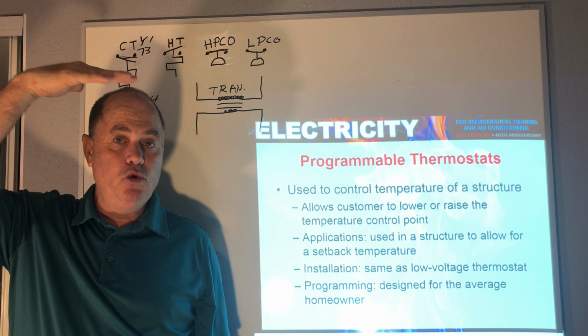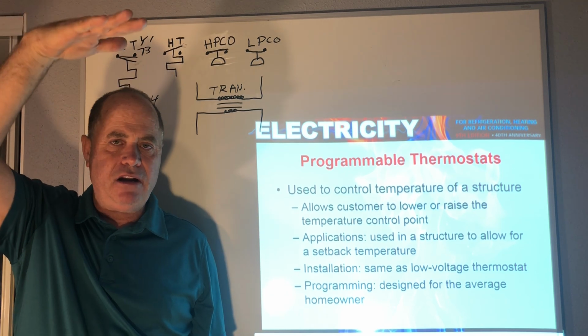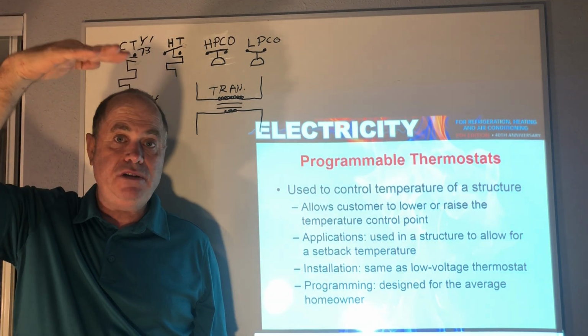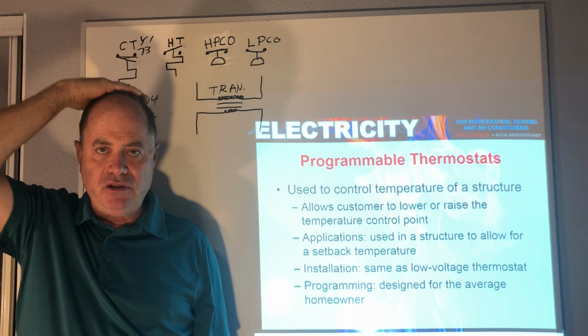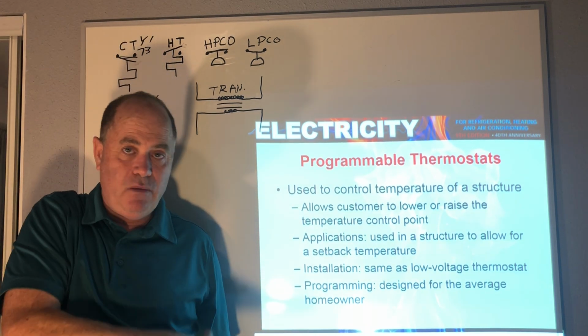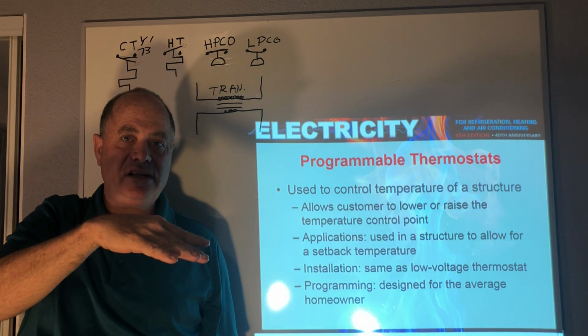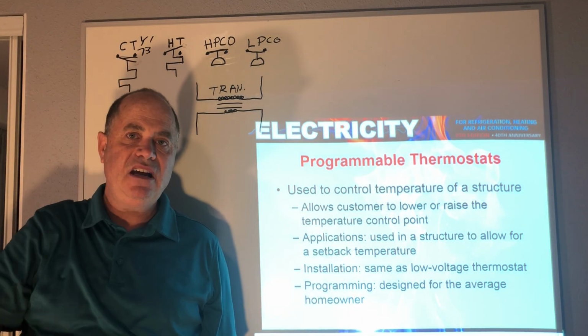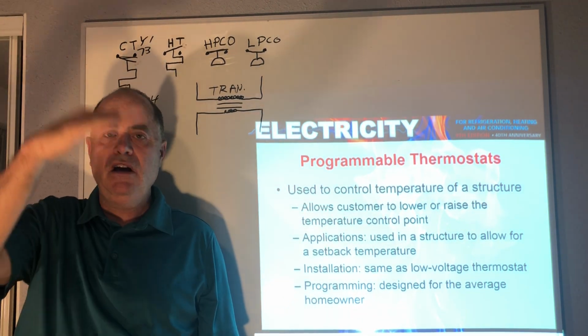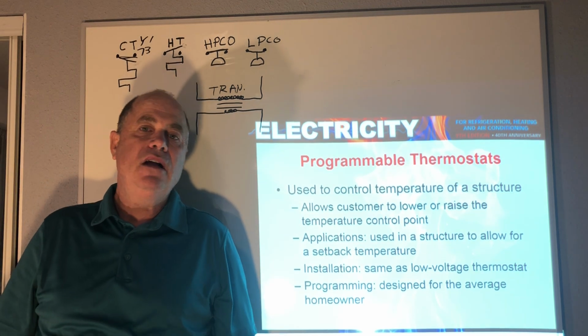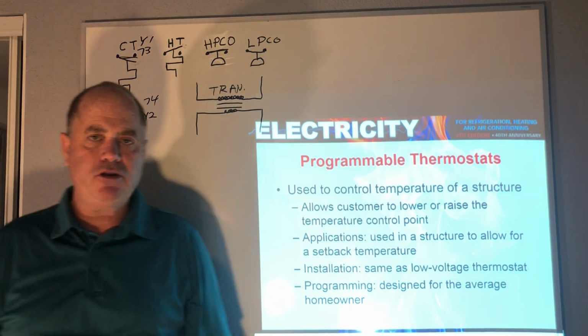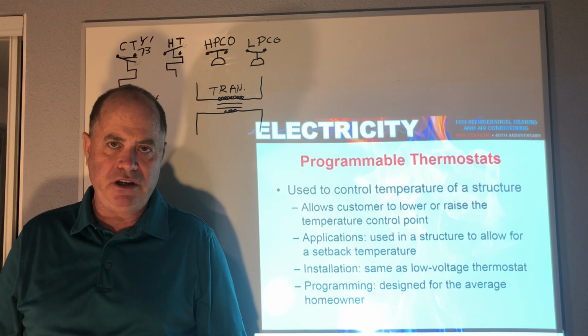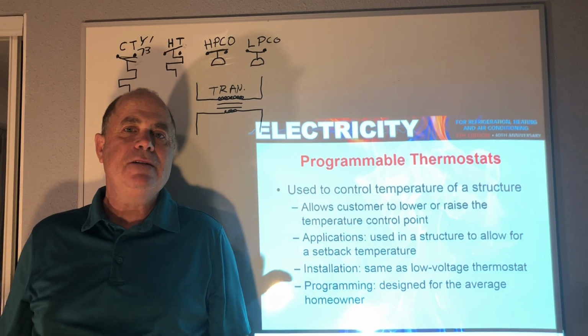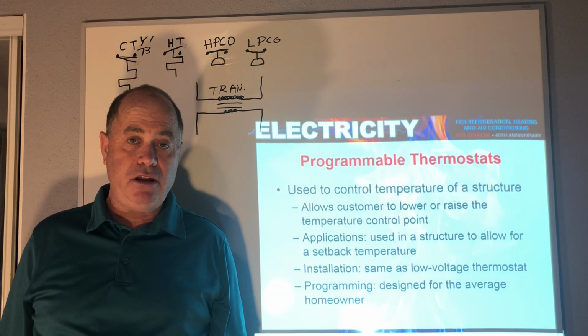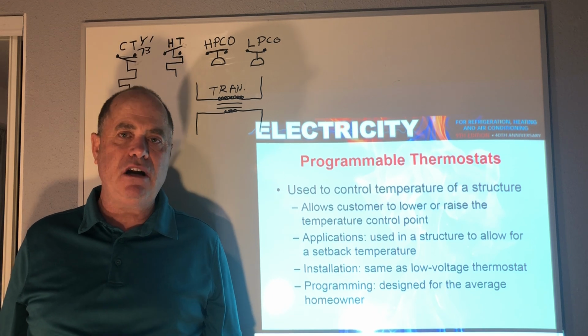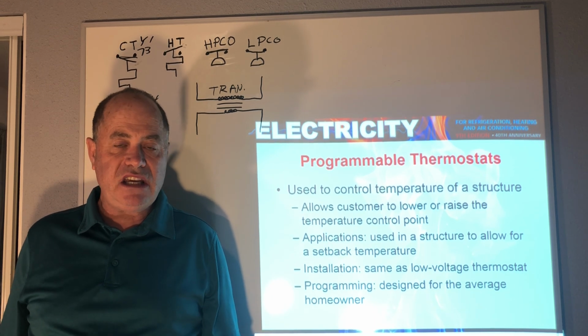Here's how we really think about it. We might say we're going to set it to be on auto, and we cool down to 73 degrees, and we heat up to 68 degrees, and maybe just between 68 and 72 or 73, we just ventilate. Okay, and that may be an acceptable temperature for people when they're occupying a building or a residence. But let's say people go to work during the middle of the day, Monday through Friday, and they're like, we don't really need to be running the air conditioning or the heating.